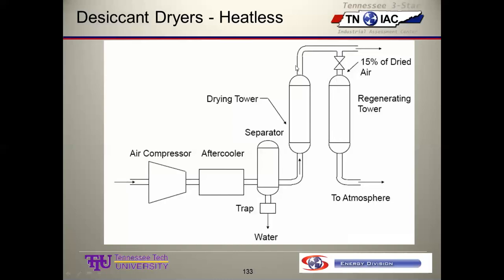So if this is a 1,000 CFM dryer, say we've got a 200 horsepower compressor back here, and this is the dryer for it, of our 1,000 CFM, if we're at full load, we're going to take 150 of it, and it's not going to go to the system. It's going to get bled through this tower and thrown away to the atmosphere to strip off the moisture, so that we can switch this in whatever length of time, and this becomes the drying tower, and this tower gets regened. And so that's the real cost of this, is you're throwing away 15% of the dryer rating almost continuously.